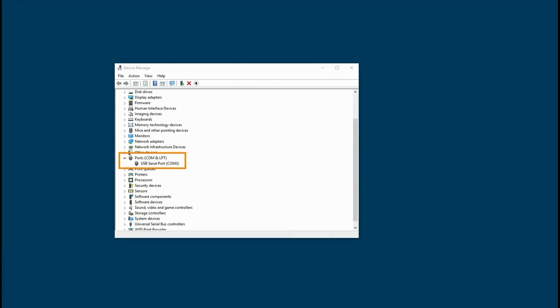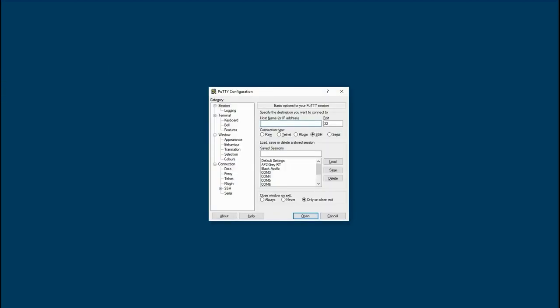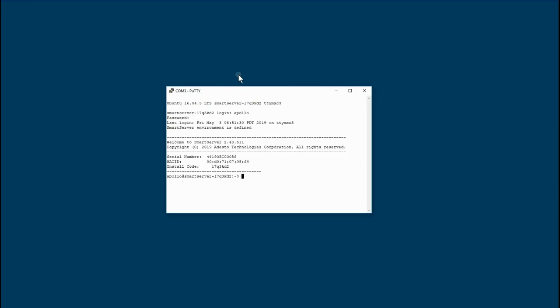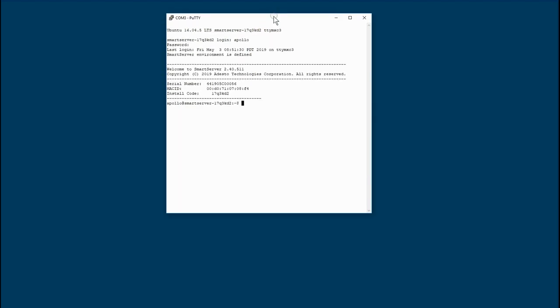Now I know that my Smart Server IoT can be reached on COM port 3. I'll go ahead and start a PuTTY session and use the serial interface to connect at 115,200 bits per second. I'll log in as user Apollo with the password that was configured on the back of my unit. From here I can do an ifconfig to learn about the IP address for the connected Ethernet port.